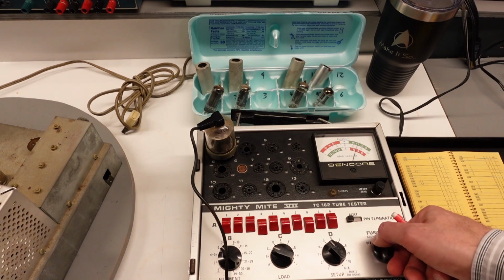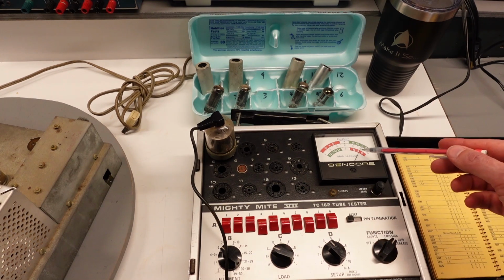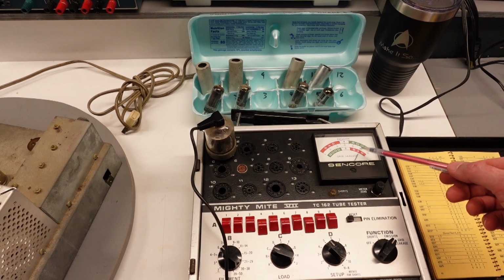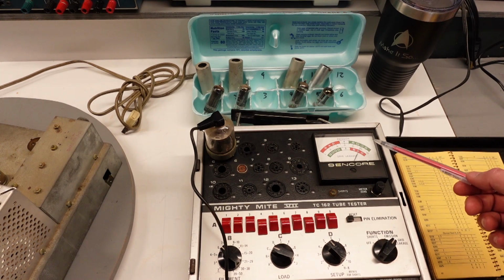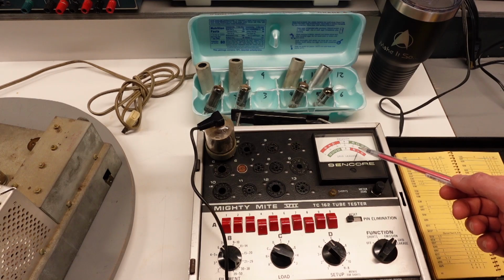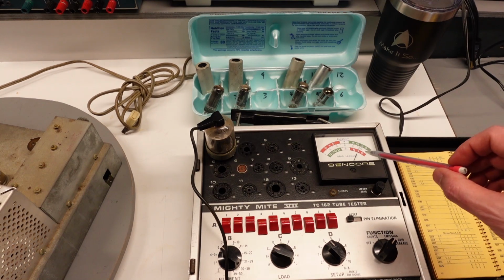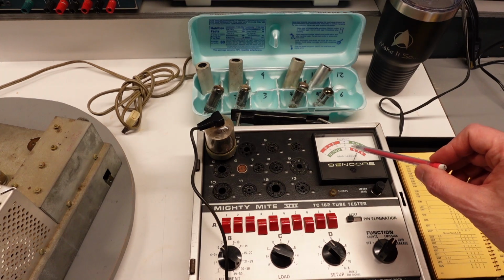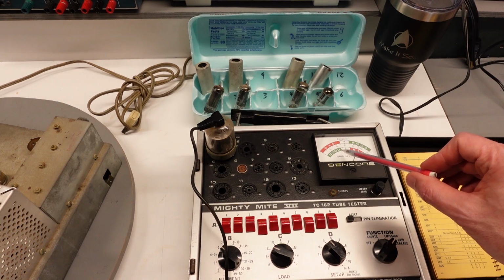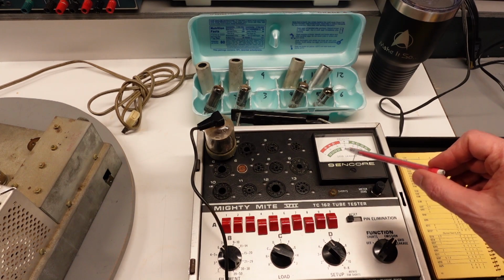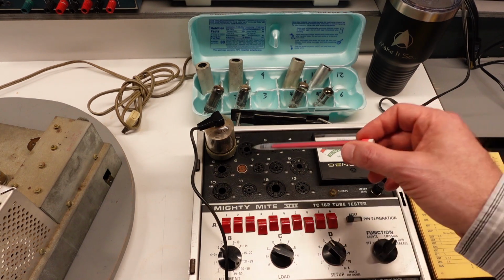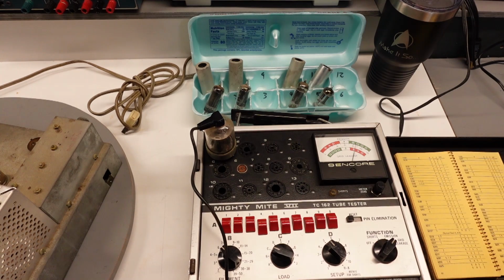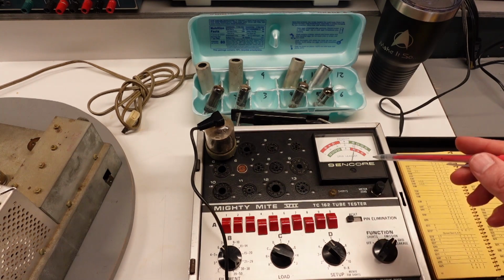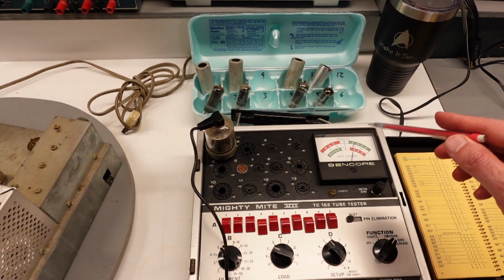Now switch it over to grid leakage, and it's in the bad region. It's the lower scale, but it doesn't stay there. I've seen a very odd behavior here. This needle will very slowly move back over to the good range, and I think it's just slowly decaying. Whatever micro current is leaking across the grid is slowly decaying. So that might be a false positive.